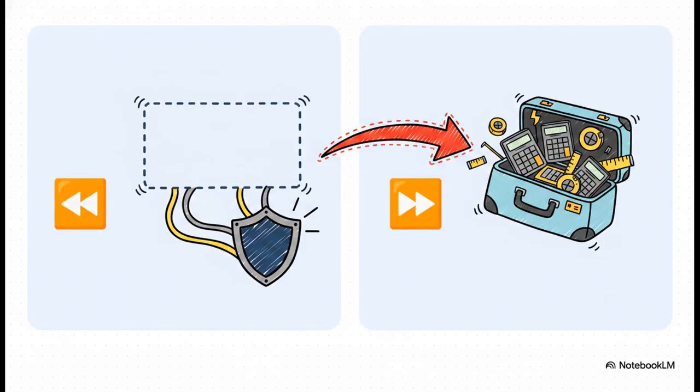Now, the most immediate structural shift you need to know for your day-to-day work, it's all about load calculations. Historically, branch circuit, feeder, and service load calcs lived right in Chapter 2 under Article 220. But in the 2026 edition, those calculations packed up their bags and moved straight into Chapter 1 to become the brand new Article 120. This is a real game changer because it fundamentally clears up Chapter 2 to focus entirely on its core mission, wiring and protection.